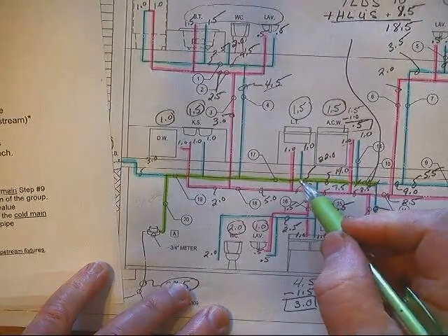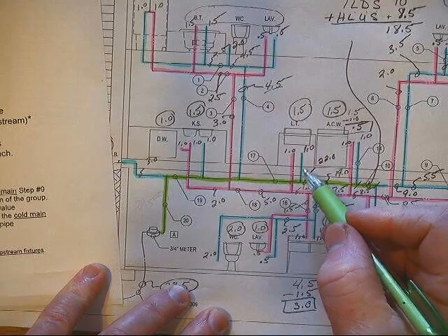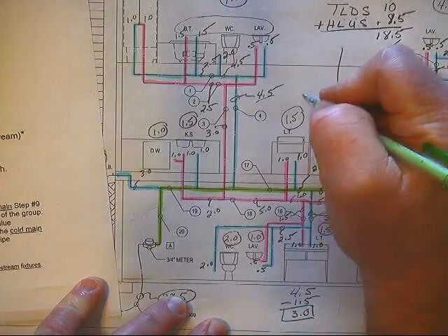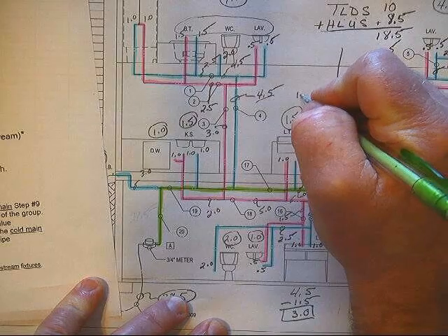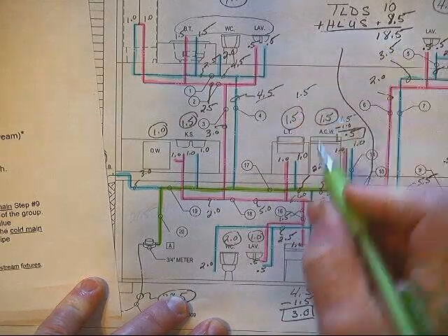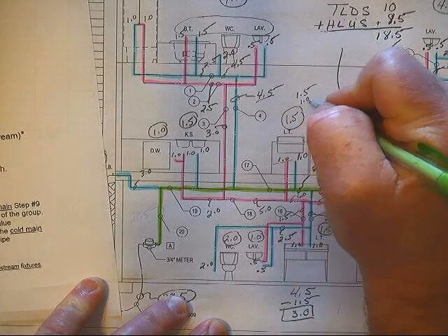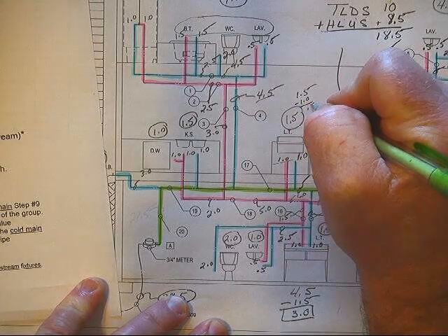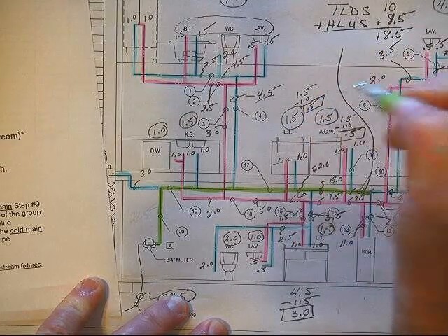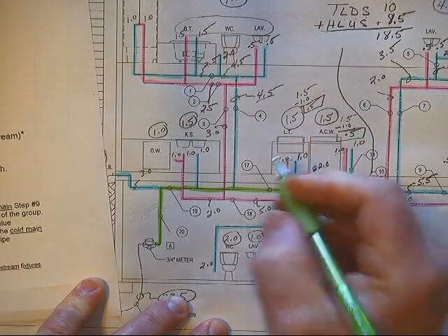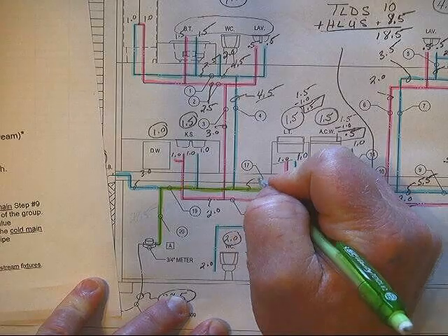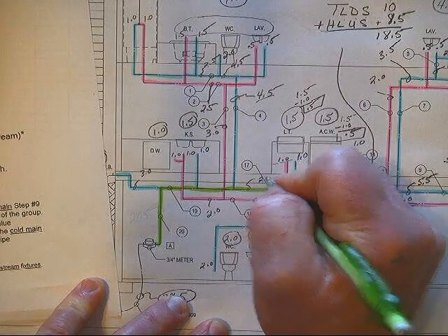We'll work back to the next branch that ties in, and in this case it happens to be the laundry tray, and that total load was 1.5. The hot load of that fixture was 1. We'll subtract it. We'll have 0.5 left over to add back on, and so we go to 22.5 on pipe number 17 here.